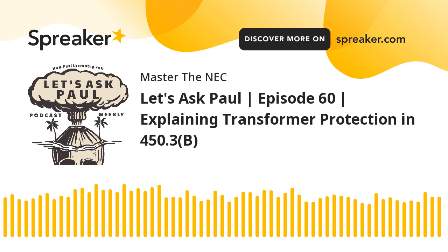Number one, this is the ampacity of the secondary conductor rules. It says those secondary conductors for this 45 kVA transformer, A says, not less than the combined calculated load on the circuits supplied by the secondary conductors. So that means that you had to do a load calc, which you should have done anyway. And that's what drove you to size the panel anyway.